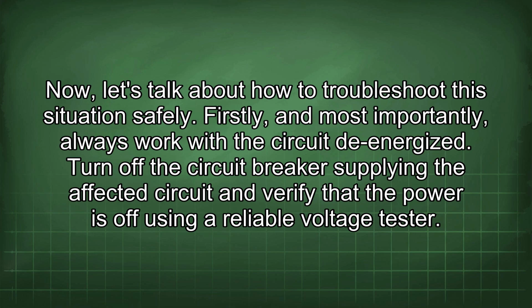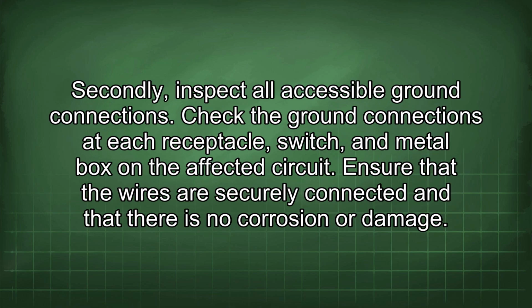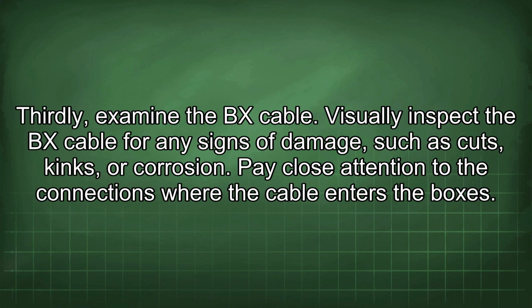Now, let's talk about how to troubleshoot this situation safely. Firstly, and most importantly, always work with the circuit de-energized. Turn off the circuit breaker supplying the affected circuit and verify that the power is off using a reliable voltage tester. Secondly, inspect all accessible ground connections. Check the ground connections at each receptacle, switch, and metal box on the affected circuit. Ensure that the wires are securely connected and that there is no corrosion or damage. Thirdly, examine the BX cable. Visually inspect the BX cable for any signs of damage such as cuts, kinks, or corrosion. Pay close attention to the connections where the cable enters the boxes.